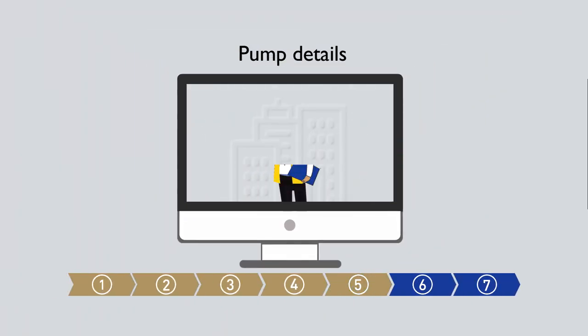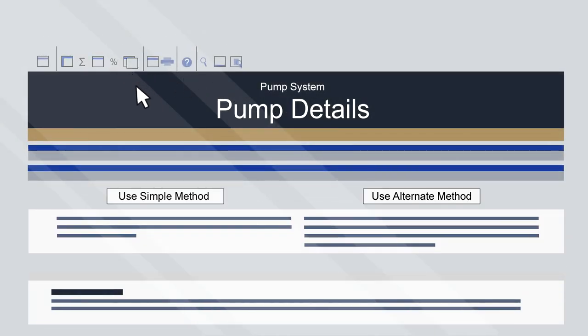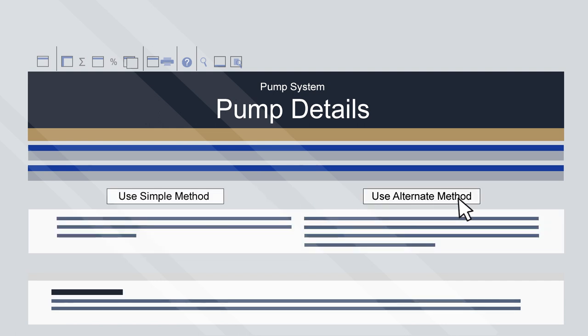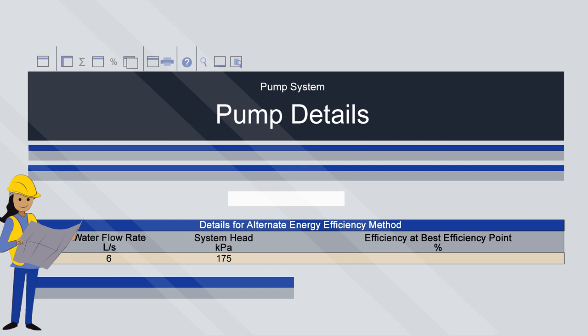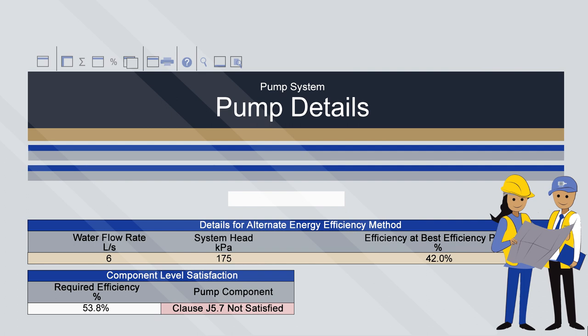Step 5: Pump Details. Navigate to the Pump Details sheet. Like the pipes earlier, for other pumps there are two options: the simple method or alternate method. The simple method can be chosen if the minimum efficiency index is known. If not, additional information about the pump's characteristics will be needed. In this example, the minimum efficiency index is not known, so the alternate method is selected. Based on this choice, enter the water flow rate, system head and the efficiency, and check the result. This pump does not satisfy Clause J5.7 at a component level; however, it can still form part of a compliance system when evaluated at a system level.